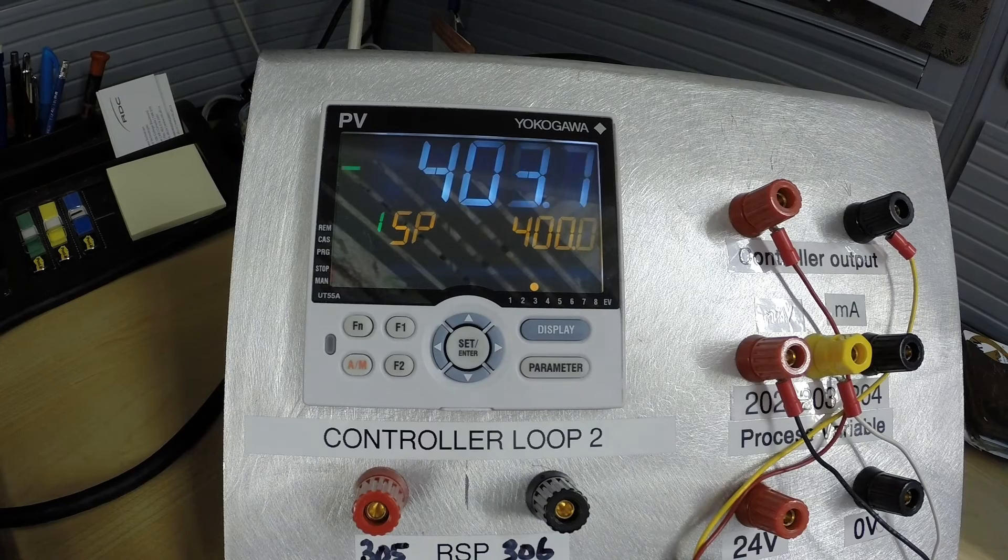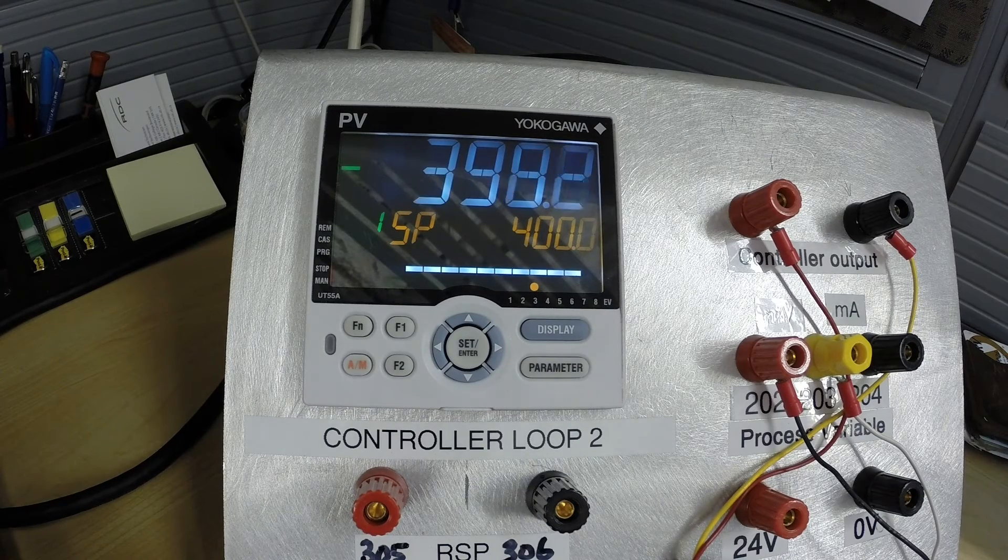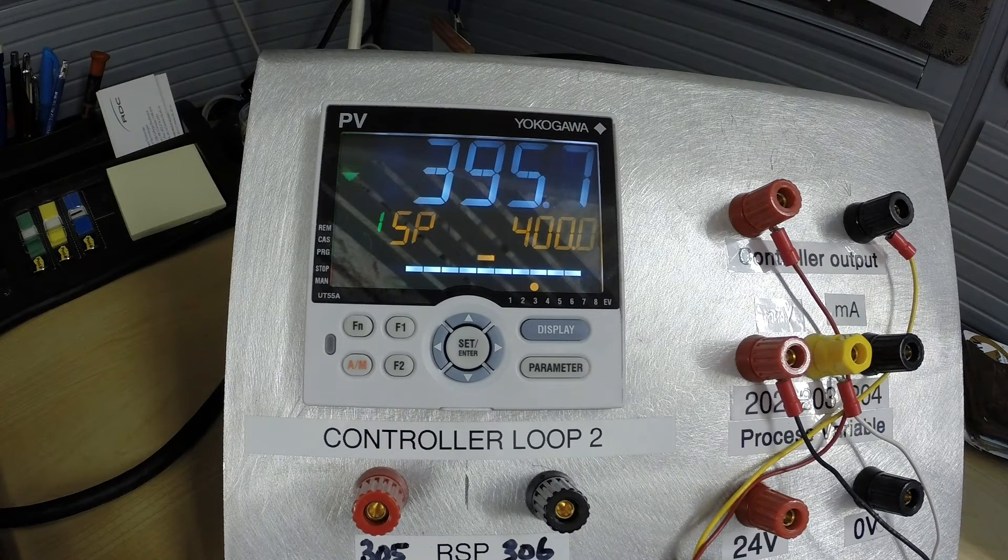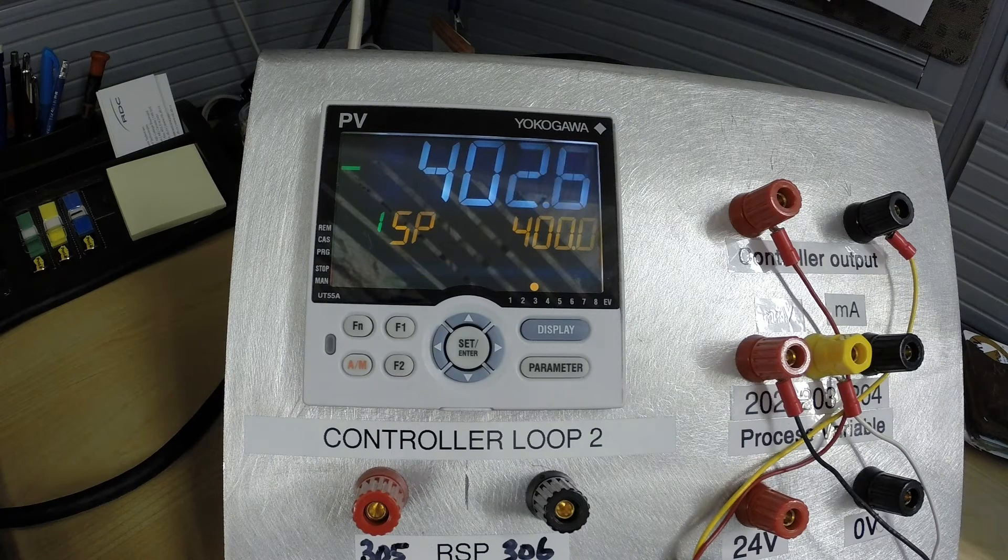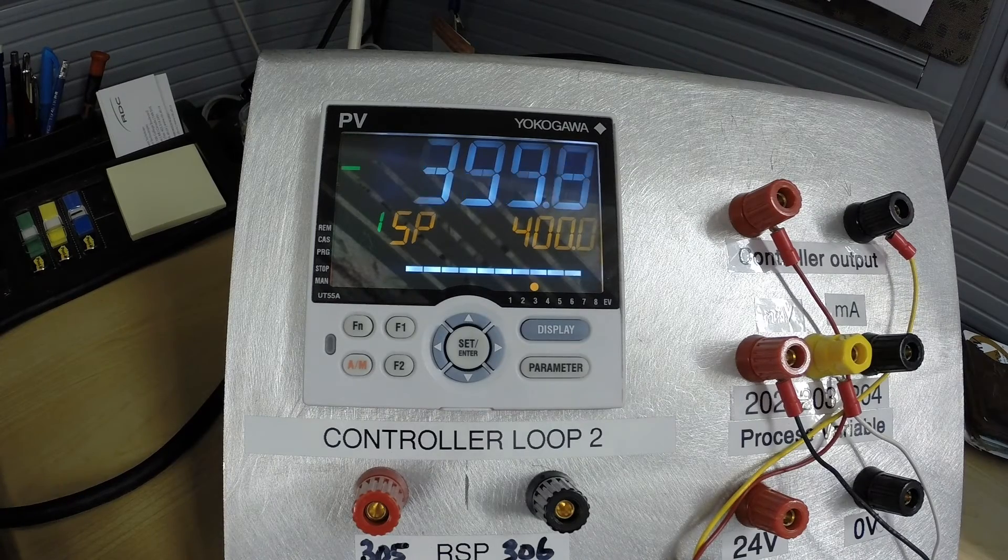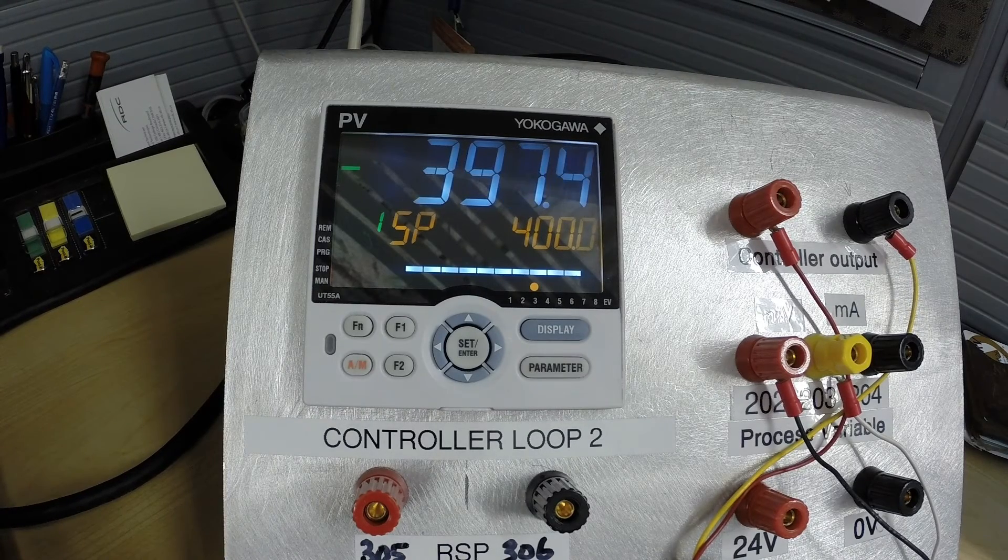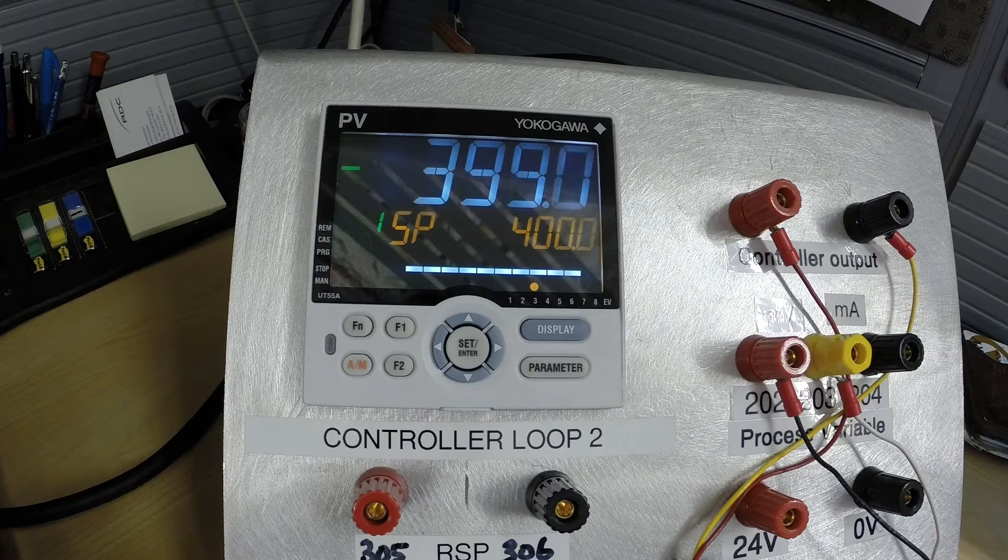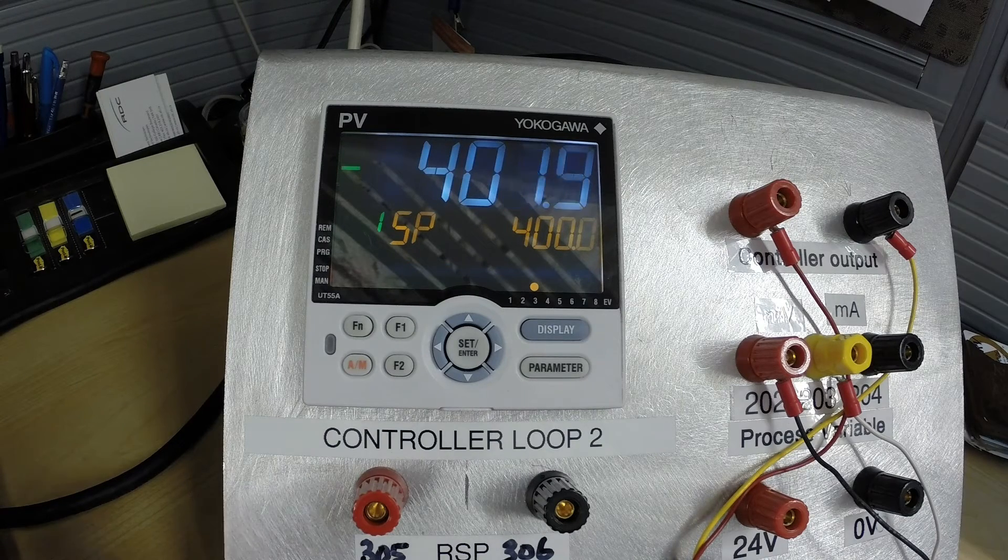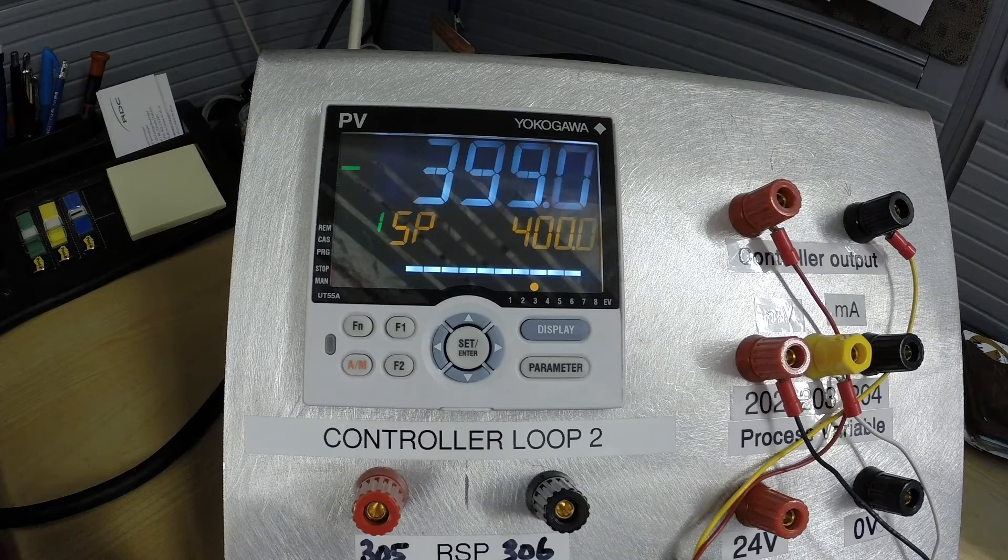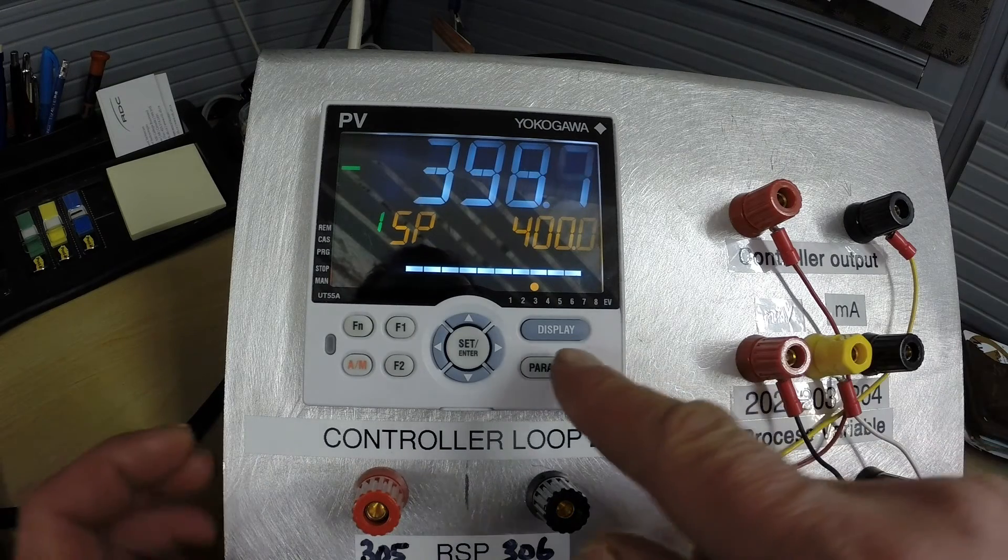Alright we now have the controller holding near our set point of 400 degrees and you can see by the large gain here that it is not tight and holding it right at 400 degrees but it is going a little bit over and a little bit under. What we want to do next is set the controller up so that we can have an alarm on a low temperature. So in order to do that we're going to go into the menu and configure some more stuff.